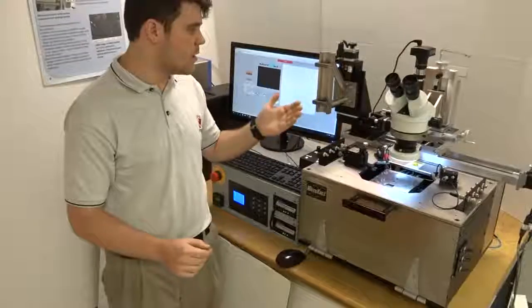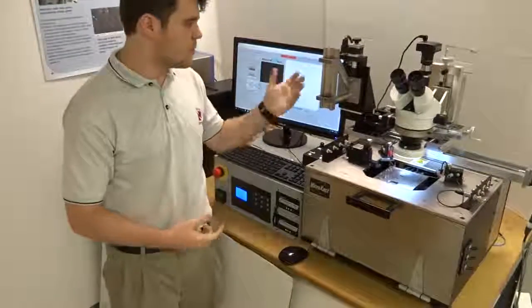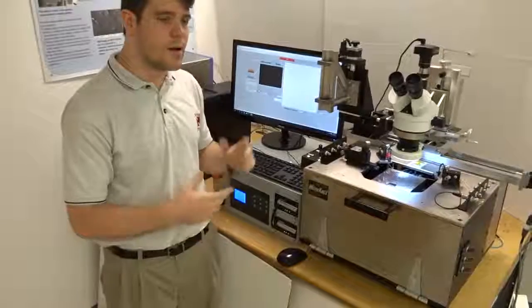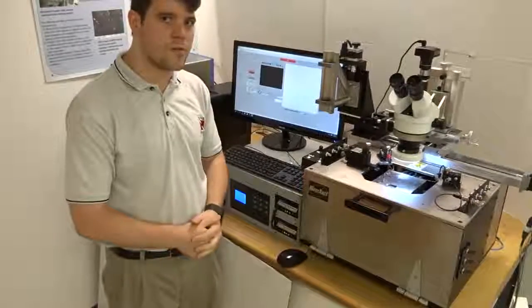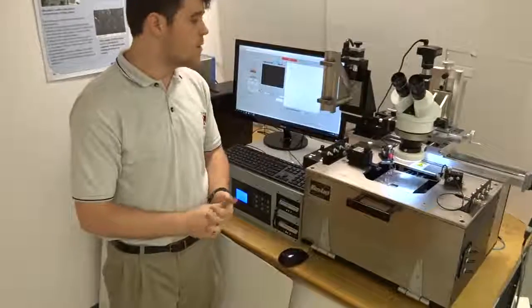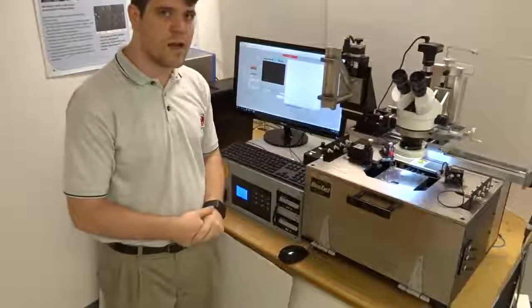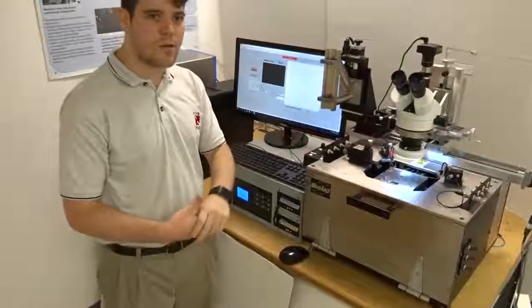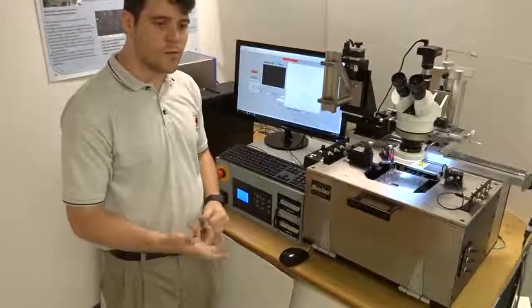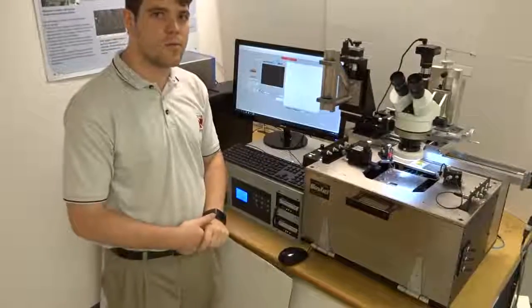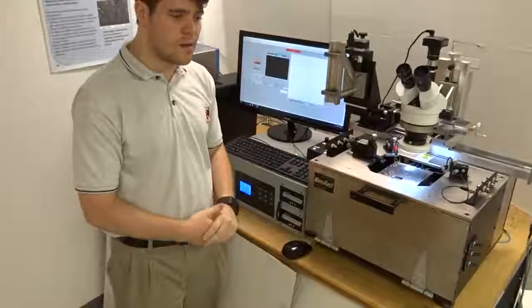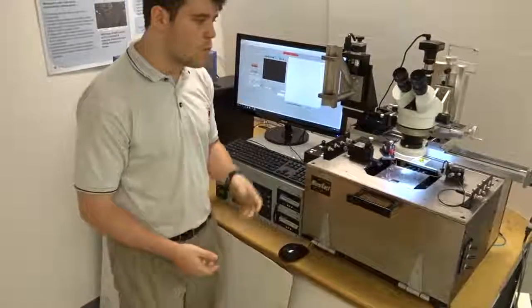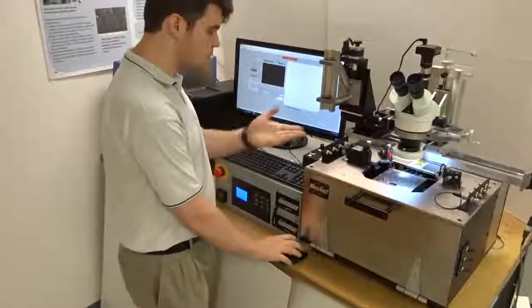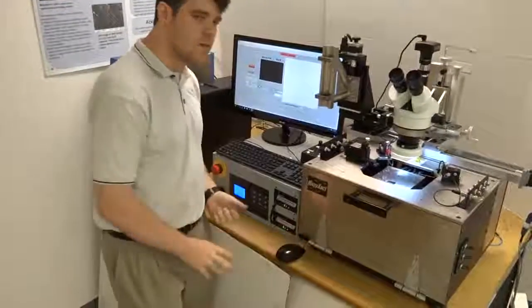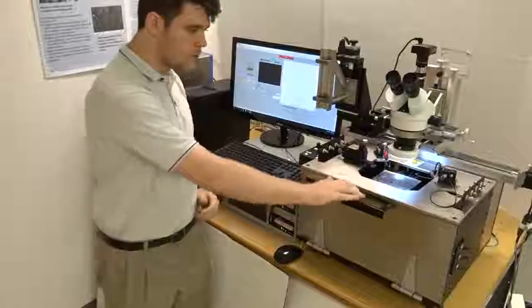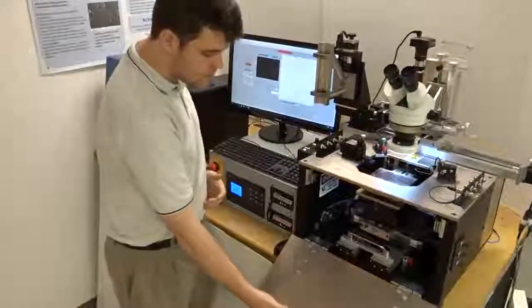We can then shift over to a second system. In this particular case, this assembly here was specified by a customer setup to then do any optical characterizations of their system that they would like to use. The system can then, once an individual die is aligned, go through and automatically test each subsequent die, and we'll be able to produce results and send them into a file that the user is then able to adjust and then get data from. Once we finish that process, we're able to then just tell the slide to go back to the load position, which it would do, and it will then move out and be ready to accept the new wafer.